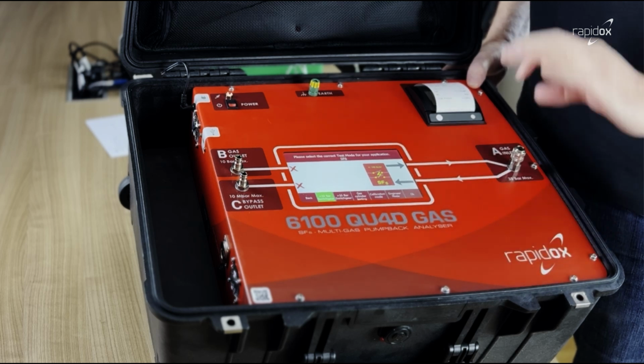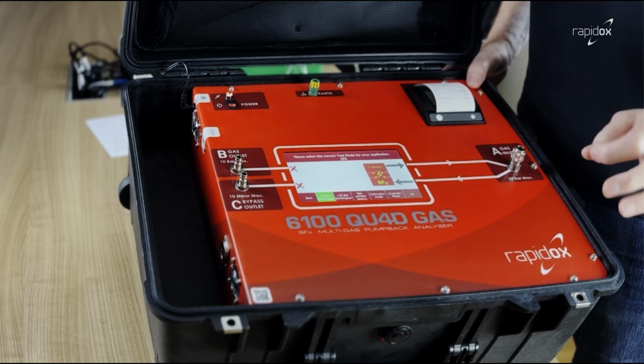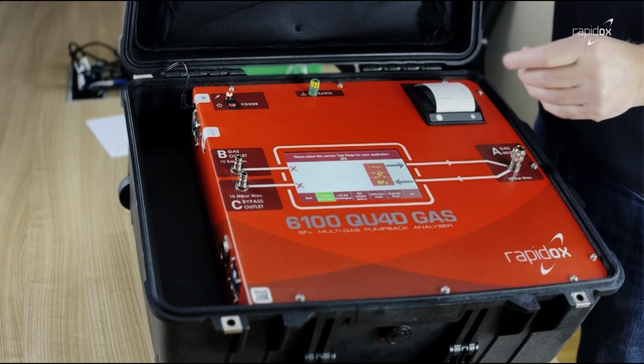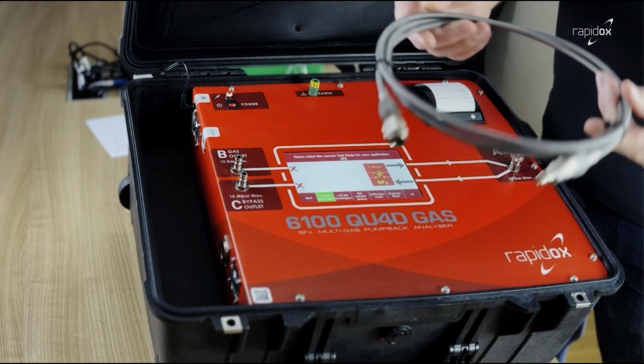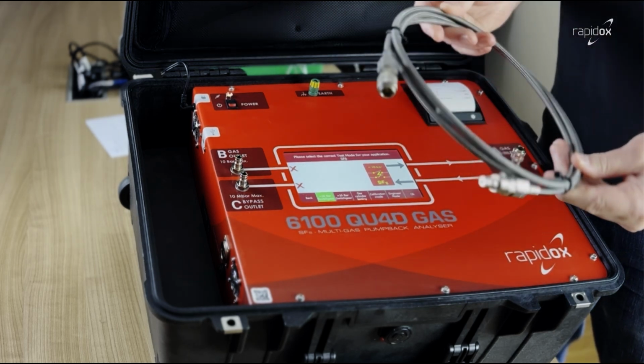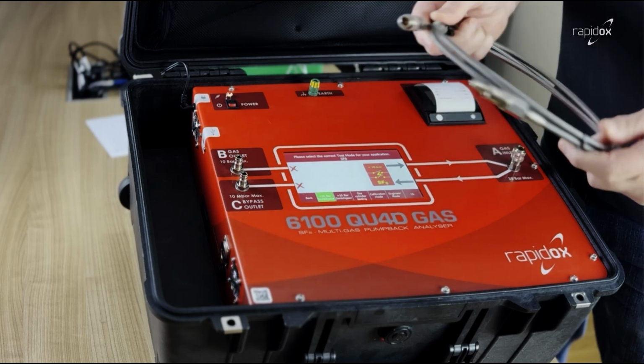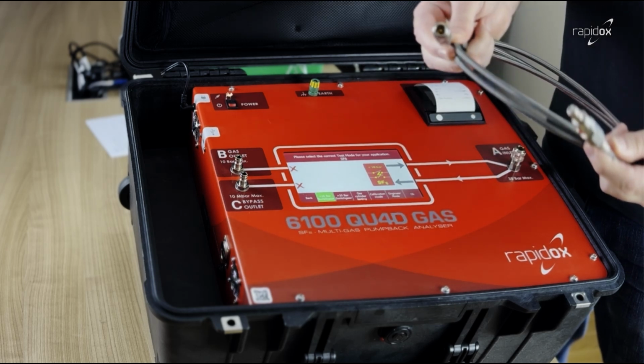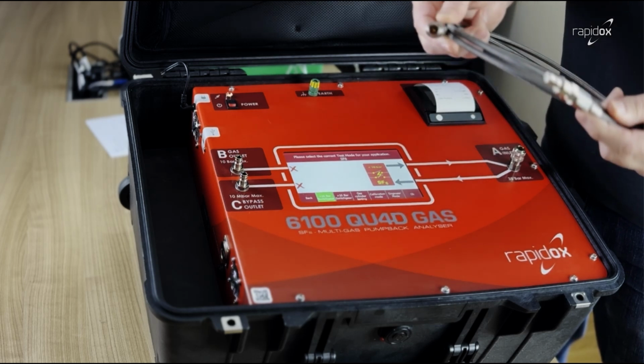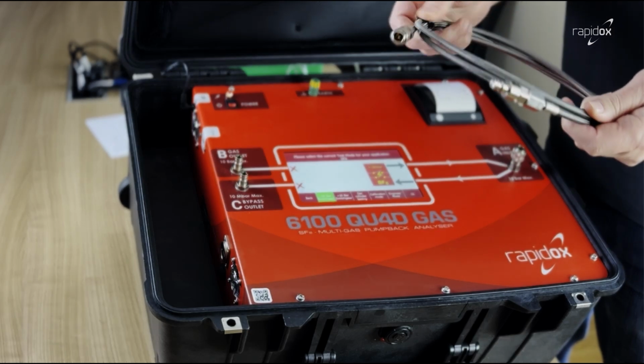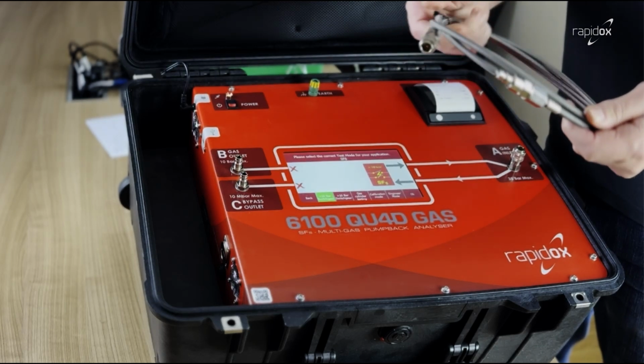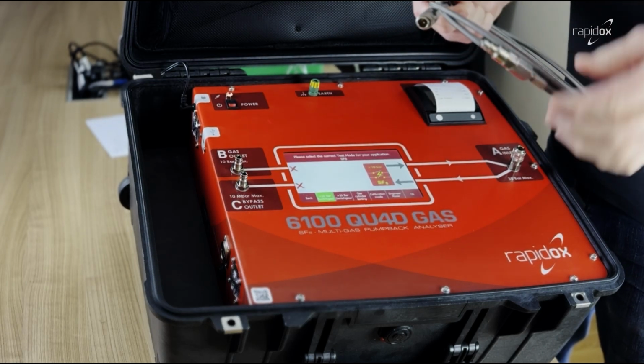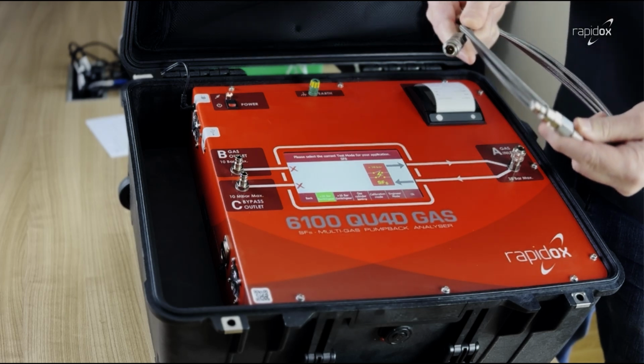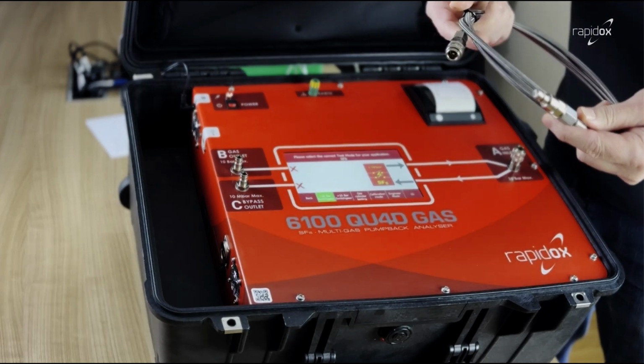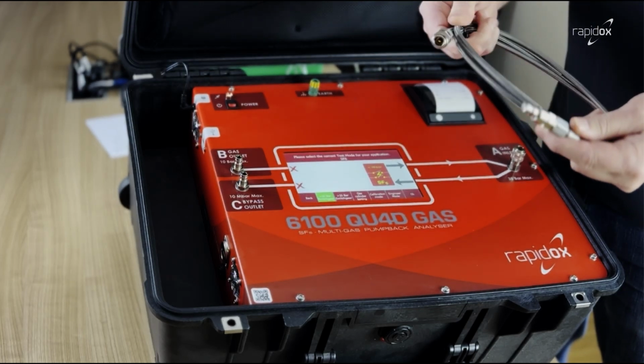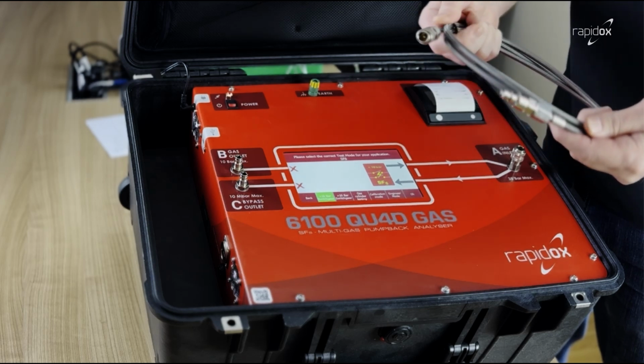It's manufactured with a special lining to be waterproof. The hose supplied with the machine is a stainless braided Swagelok type hose with rectus fittings on each end, which are compatible with nearly all switchgear in the world with the right couplings. These are very highly compatible connectors used on many gas analyzers in the SF6 industry and alternative gas industry.